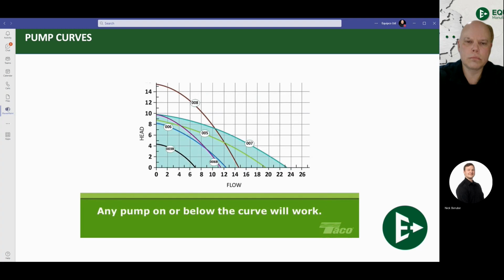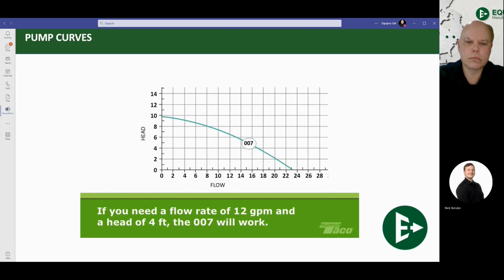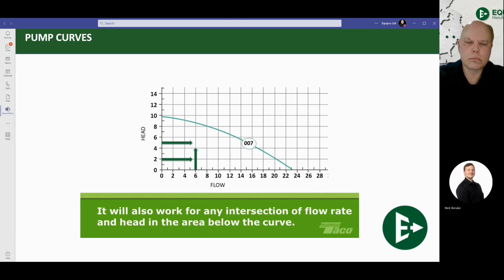Reading the pump curve makes it easy to choose a pump for a particular hydronic system. Technically, if the head and flow operating point of your system is located on or below a given pump's performance curve, then that pump will be sufficient to do that job. So if your system requires a flow rate of 12 gallons per minute and a head of 4 feet, the 007 will easily meet those requirements. It will also meet the system requirements if you need a flow rate of 6 GPM and a head of 2 feet, or 5 feet, or any other intersection of flow rate and head in the area below the curve.